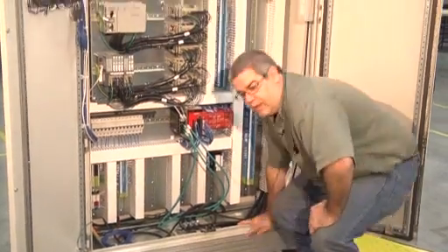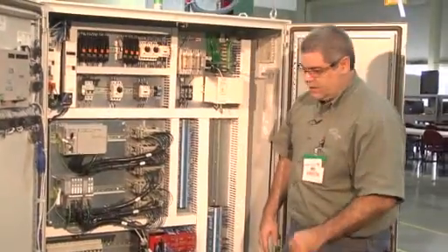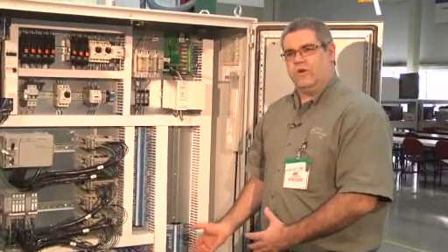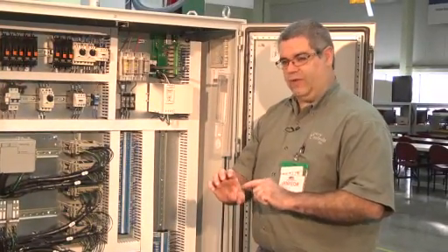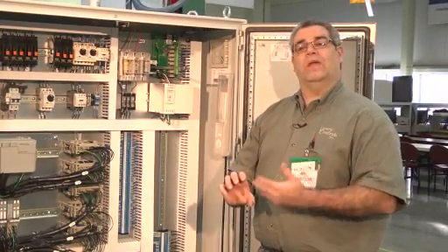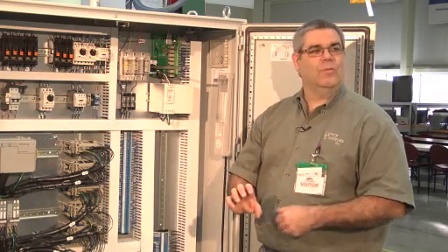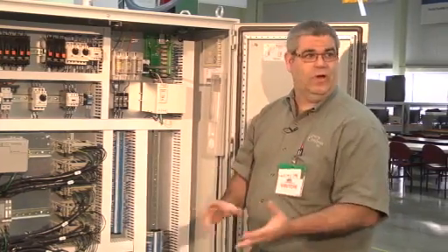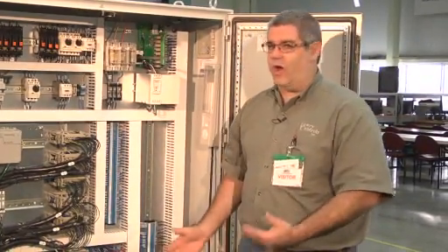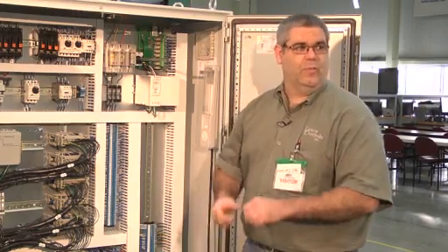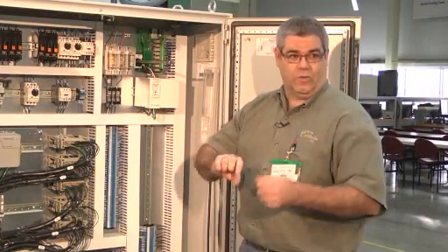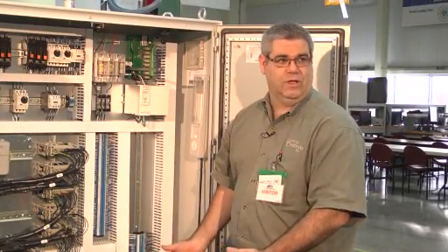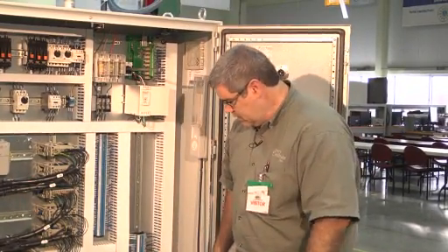And those jumpers are, I'm trying to think of the right way to say it, but those terminal relays have jumpers on them, and those jumpers are making the relay run backwards. Some of them are in reverse. So by habit of knowing 11, 14, 12, the contacts and the coils going through them, they're not all wired that way. So some of them have jumpers and inverted the signal going the wrong direction. It's very low voltage, very low current, so it's purposely done for troubleshooting. You've got to follow the drawings.